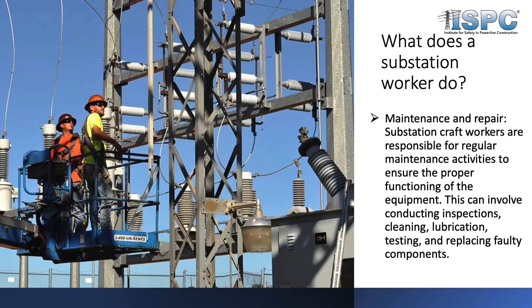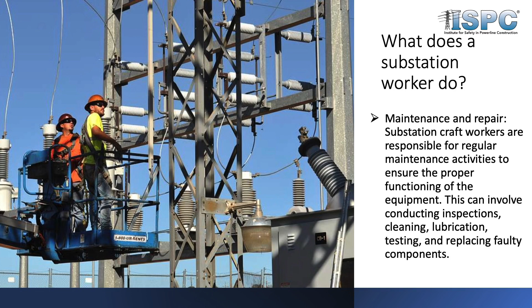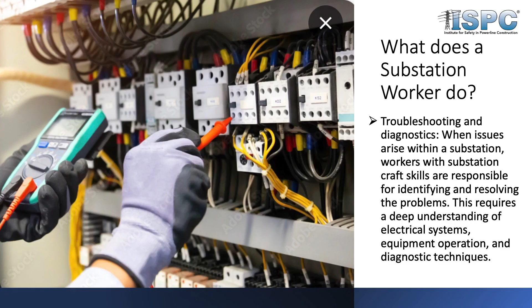Maintenance and repair. This is probably what most people think about when they think of substation electricians. The substation's up and running, in service, and we maintain it. We do inspections on a regular basis—weekly, monthly, quarterly, whatever the case may be. We proactively take equipment out of service to perform cleaning, lubrication, and testing. We could be doing timing tests on circuit breakers, or oil testing on power transformers. It could be equipment found to be faulty, through infrared inspections finding hot spots, things of that nature, that we need to take out of service and fix. So maintenance is a big aspect of the substation worker's daily tasks.